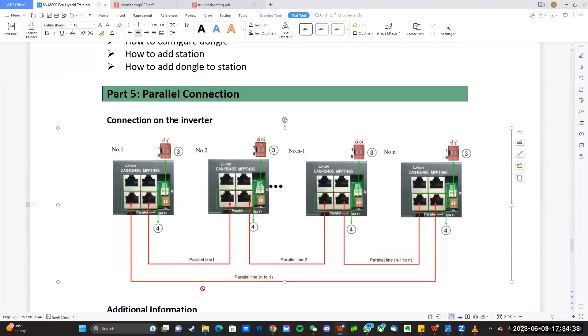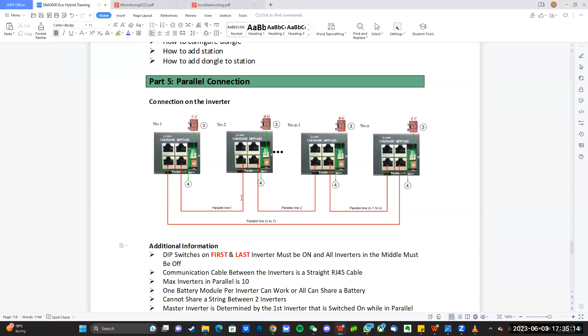This is a diagram of 4 units in parallel. On the bottom ports, these are your parallel ports where the comms cables connect, using straight RJ45 cables plugged in here. On the master inverter, bottom left, and the last slave inverter, bottom right, these two connect together, and the ports in between connect together, daisy chaining one by one.